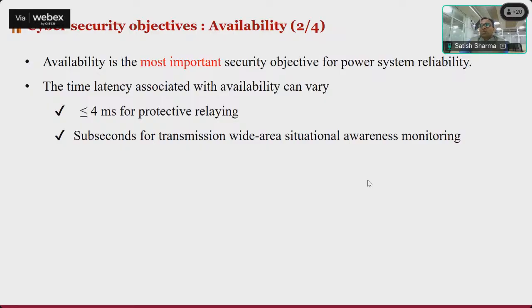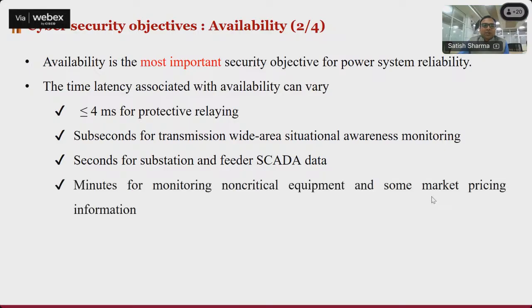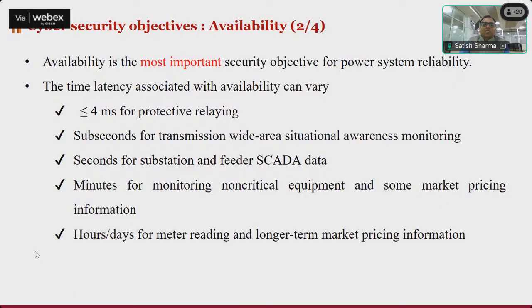So yes, time latency is there with the availability. Even if you stop certain signal or data for just a few seconds, it will affect the entire operation. Seconds for substation and feeder SCADA data, minutes for monitoring non-critical equipment and some market price information, and hours or days for metering, since it's not like every second data is fed to the distribution company. Generally, they have a 5 minute or 10 minute interval in which they take the meter readings.